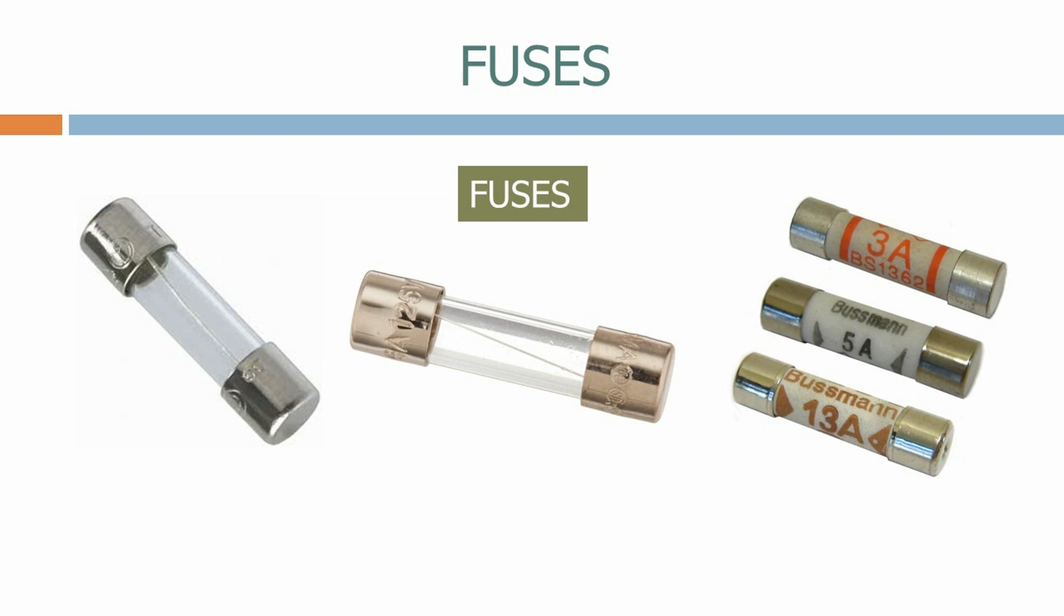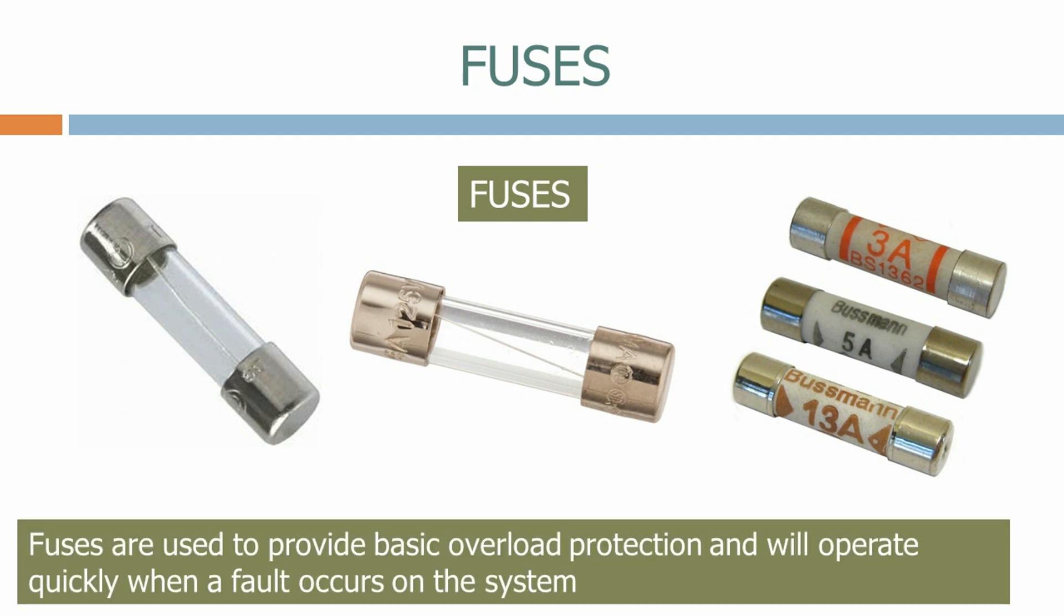We achieve different fuse ratings by changing the diameter of the wire inside the fuse. As the wire diameter increases, so does the fuse rating, as a larger diameter wire will melt at a higher current magnitude. Fuses are used to provide basic overload protection and will operate quickly when a fault occurs on the system.